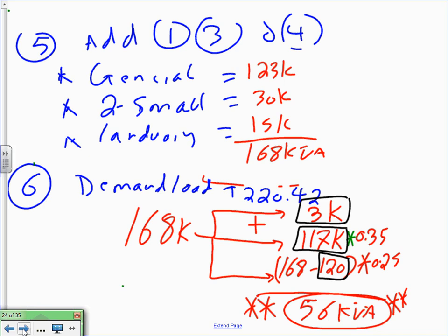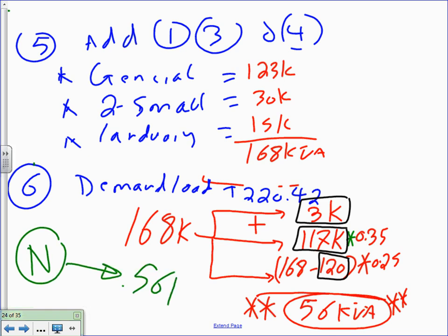So, neutral size. I would like you guys to size the neutral like we did before. For neutral, the same number, 56 kVA. Done. No derating, nothing. 56 kVA, no change on that one. Cool? 56 kVA. Why? Because the small appliances circuit, light and laundry are 120. Can I have the thumbs up for this one, Chad?